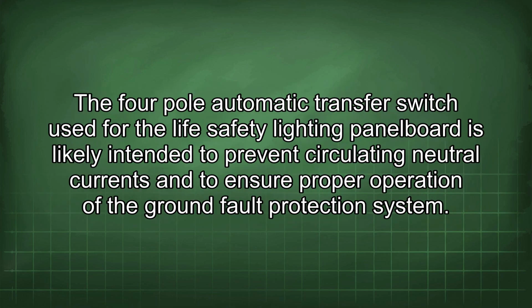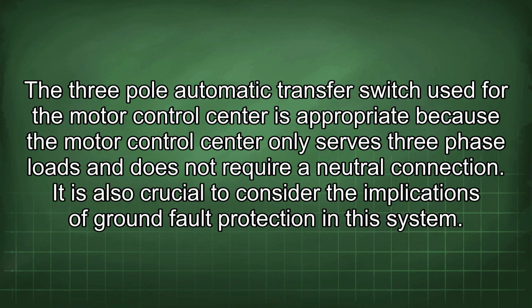The 4-pole automatic transfer switch used for the life safety lighting panel board is likely intended to prevent circulating neutral currents and to ensure proper operation of the ground fault protection system. The 3-pole automatic transfer switch used for the motor control center is appropriate because the motor control center only serves 3-phase loads and does not require a neutral connection.